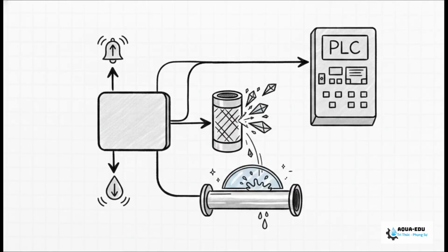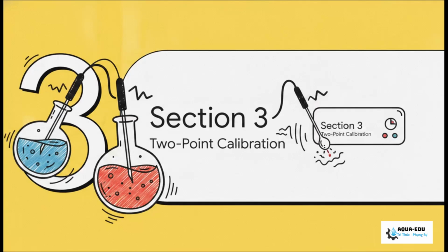It's either going to be 24 volts DC loop-powered or 230 volts AC. You'll wire your 4 to 20 milliamp analog signal back to the PLC or SCADA system, but pay extra special attention to setting those relay alarms. Triggering that high alarm at 8.5 pH, that is exactly what saves our ridiculously expensive RO membranes from carbonate scaling. And setting the low alarm at 5.5 pH is what protects our stainless steel piping from acid corrosion. It's a big deal. Let's move into Section 3, the two-point calibration process.